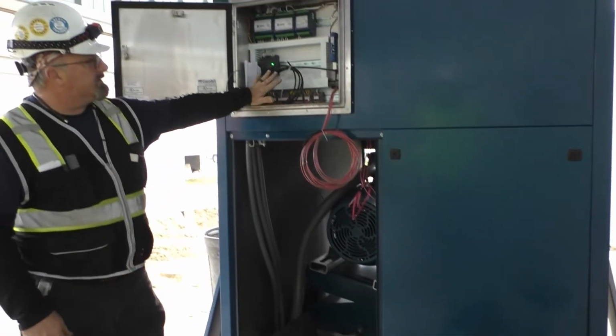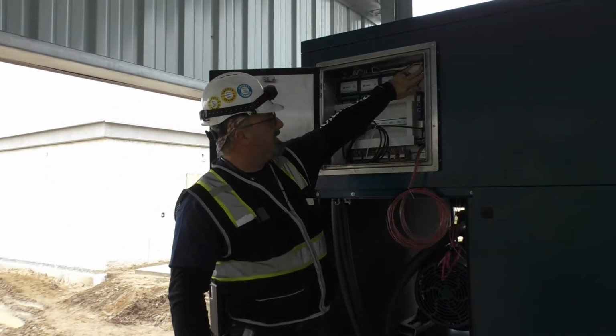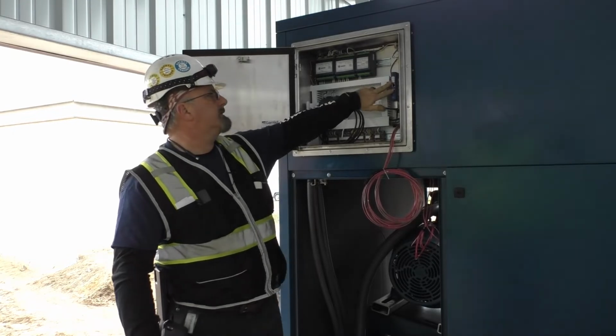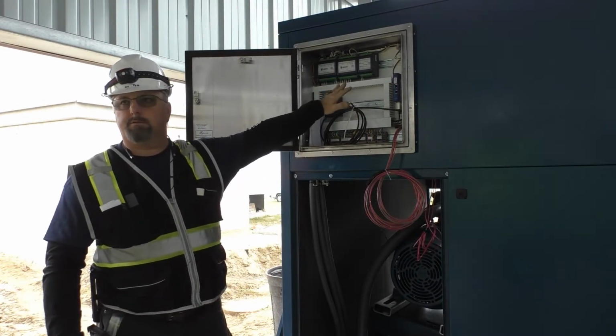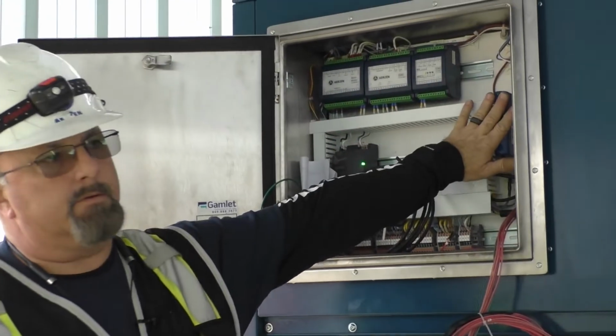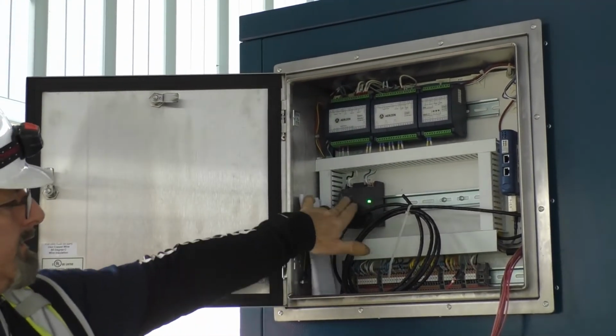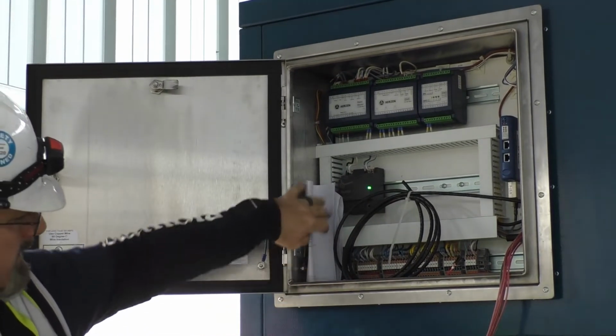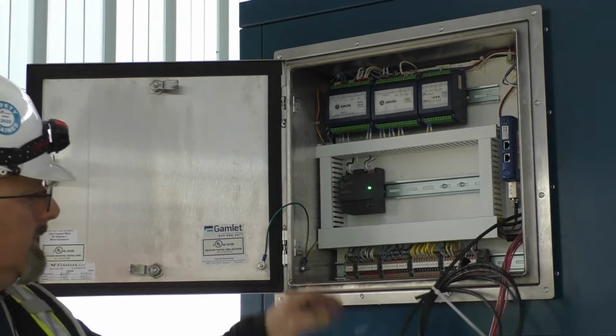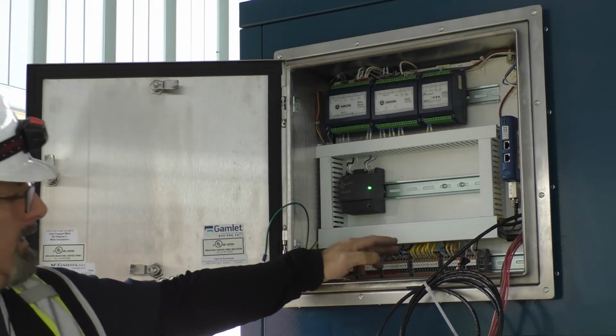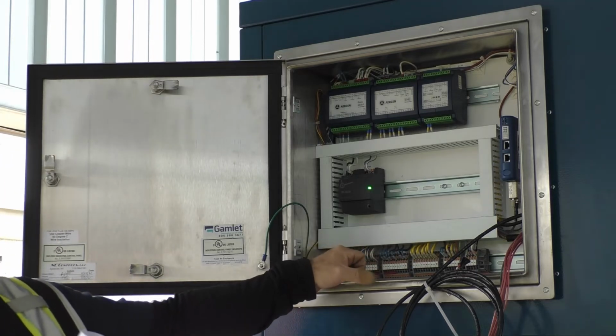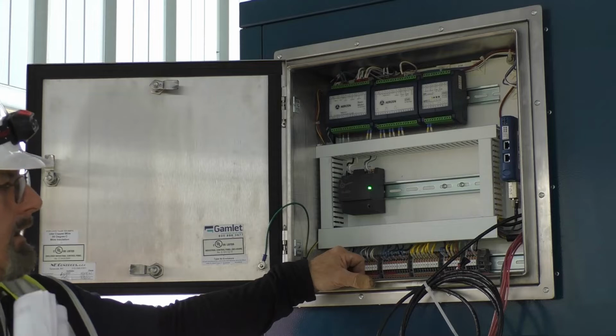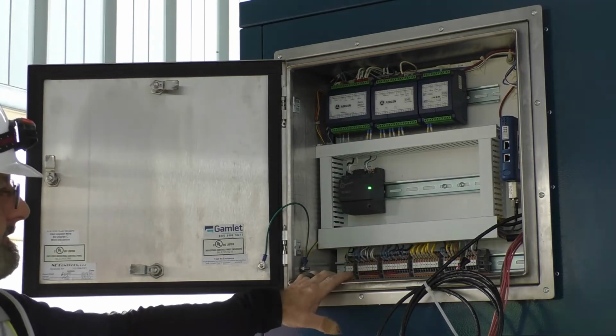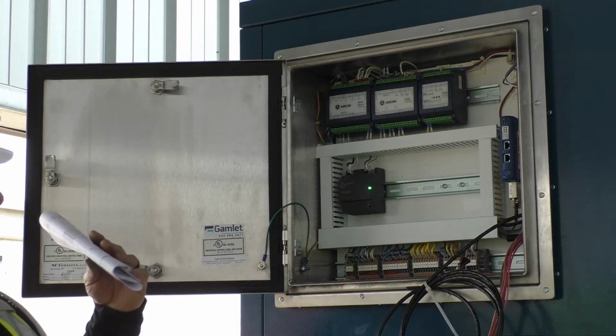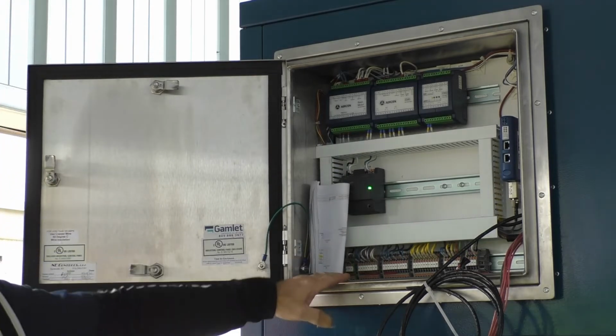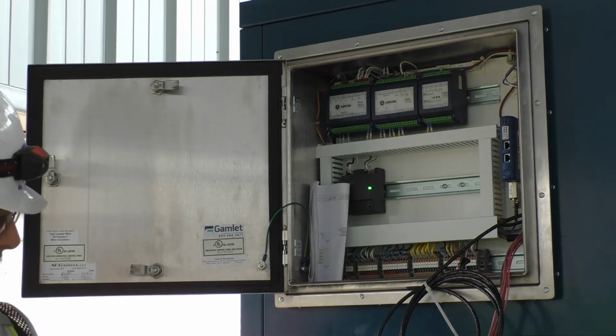All right, inside here is your control panel. You have your 2 pressure transducers, you have your Ethernet communication, and then you have the control modules that relay those functions through the Ethernet connection to SCADA. This right here is your 24 volt power supply. As you look at the terminal block, you have your incoming control power. There will be a couple more wires connected up here for communication to the VFD, but everything else will go through the Ethernet connection. You likely will never have to come in here unless there's an issue, but I wanted to give you an overview of what was back here.